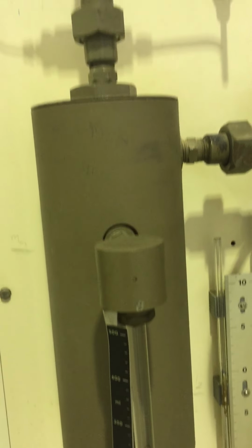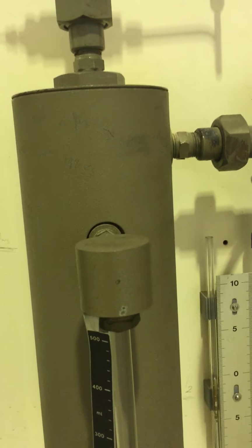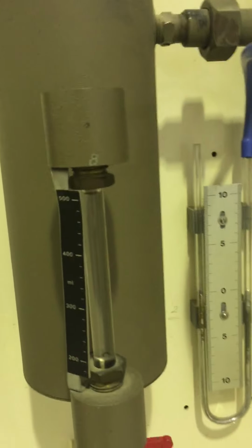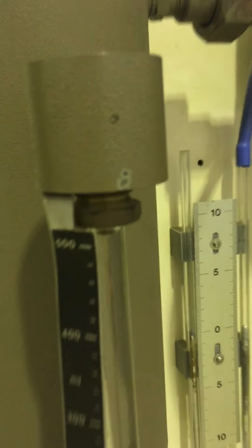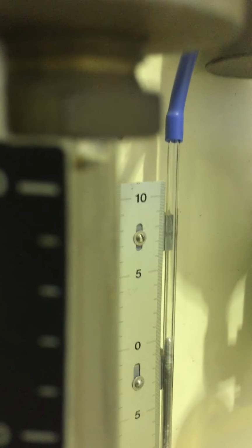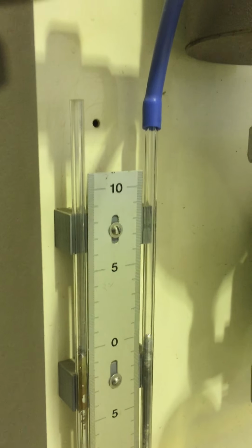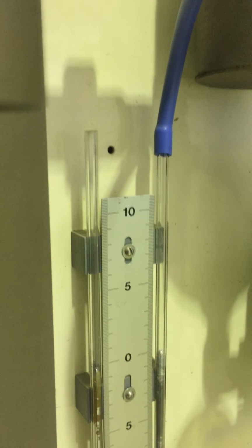In this calorimeter, the steam changes direction in the flow, and the water will be separated from the dry steam and accumulate at the bottom of the separating calorimeter. And you can see this glass tube will show the level of the water separated, and we can read the value of the separated water in cc, and the symbol we use is MWS. MWS means mass of water separated in the separating calorimeter.